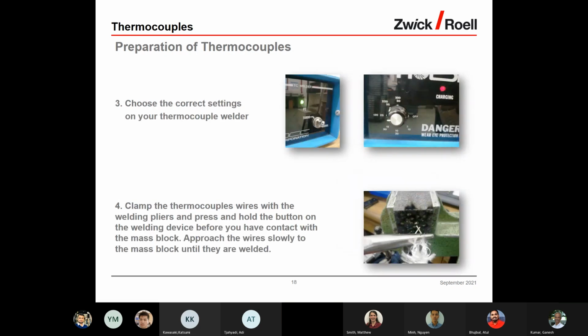Choose the correct setting on your thermocouple welder. Here you see the turbo, and here are the degrees on this side of the picture. Clamp the thermocouple wire with the welding pliers, and press and hold the button on the welder before you have contact with the mass block. Approach the wire slowly to the mass block until they are welded. This is in the lower picture here.